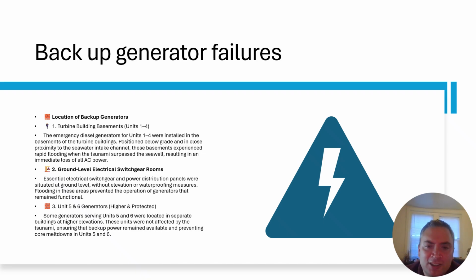Also, the backup generators failed. This is mainly due to the fact that for units 1 through 4, the emergency diesel generators were installed in the basements of the turbine buildings. Positioned below grade and in close proximity to the seawater intake channels, these basements experienced rapid flooding when the tsunami surpassed the seawall, resulting in immediate loss of all AC power. Ground level electric switchgear rooms: essential electrical switchgear and power distribution panels were situated at ground level. Without elevation or waterproofing measures, flooding of these areas prevented the operation of the generators that remained functional.